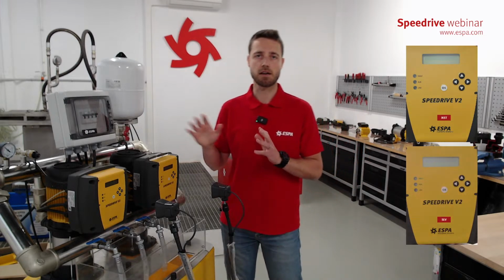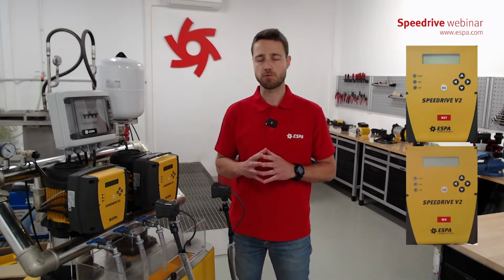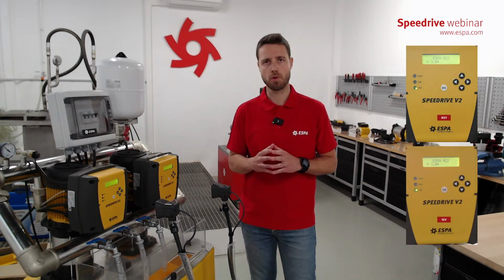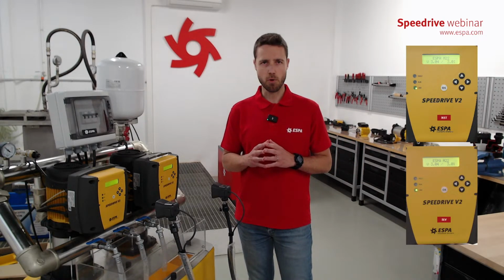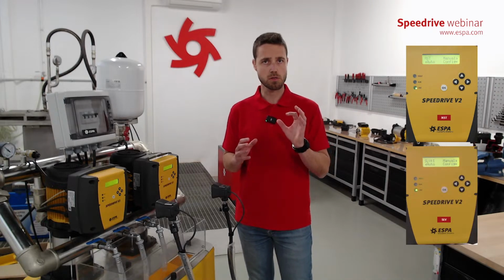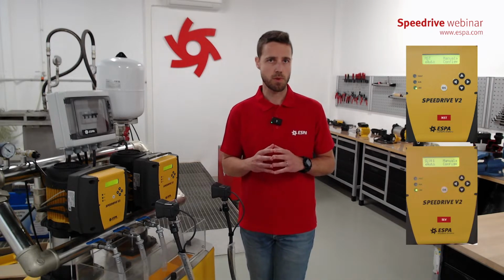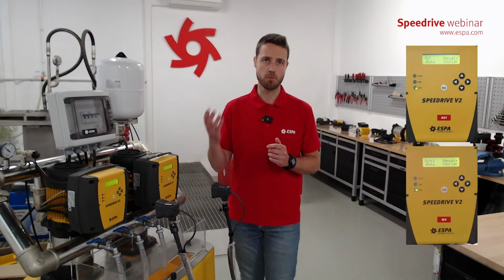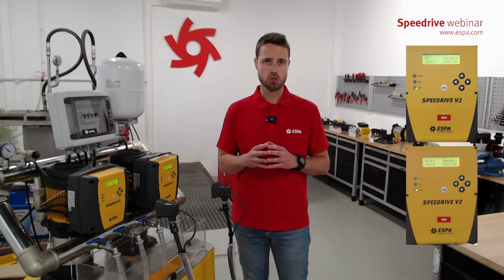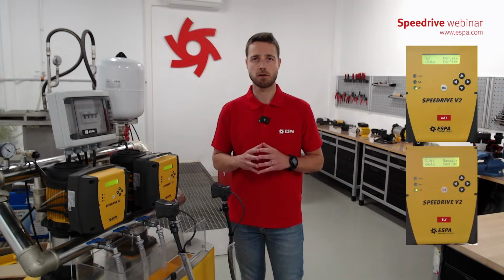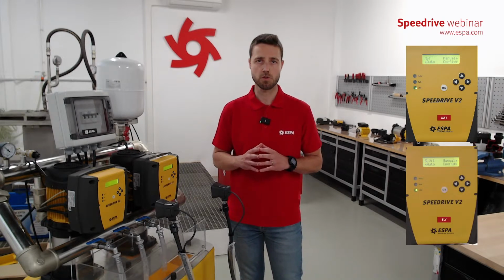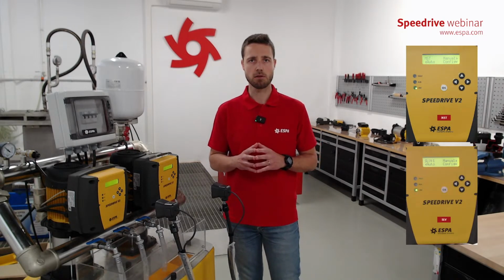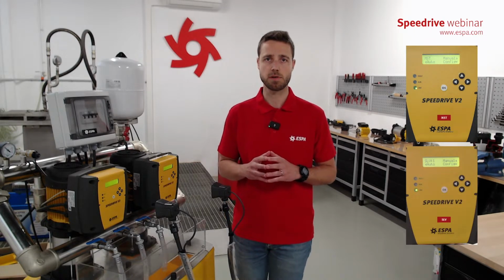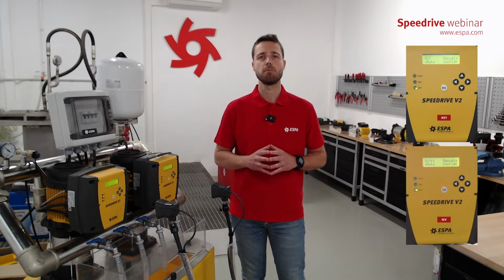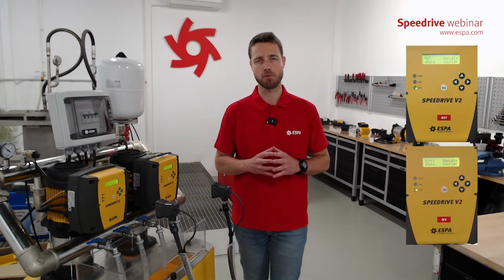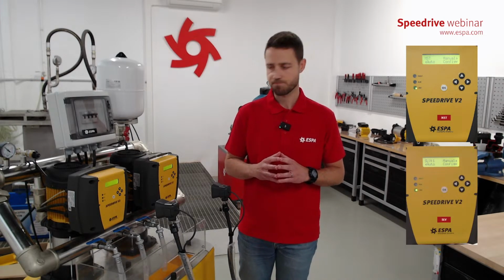Meanwhile, both Speedrive are starting. We also have to talk about the suction side. It's important always to have a good pipe diameter. It normally has to be the same size or bigger than the suction of the pump. The speed of the flow circulating on the suction side must be around 1.5 meters per second. It shouldn't be higher, because we can create problems in the flow during the suction.